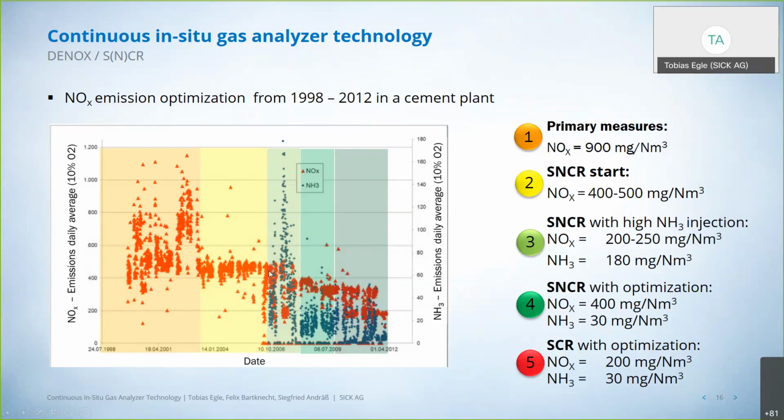So this was not at all fulfilling the requirements of the local authority. So they moved back to an ammonia slip of 30 milligrams and 400 milligrams per cubic meter, which was perfect and good enough for that time. But having the future in mind, this plant has been one of 2 pilot projects in Germany to reduce and fulfill the new regulation from 2019.